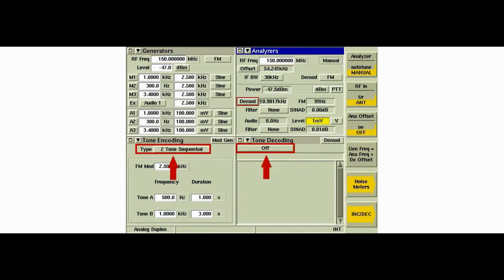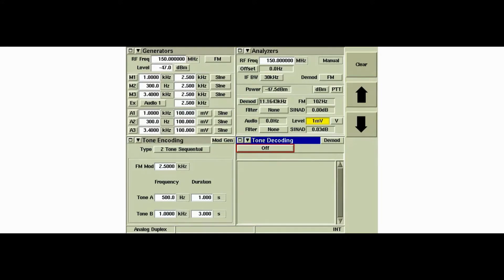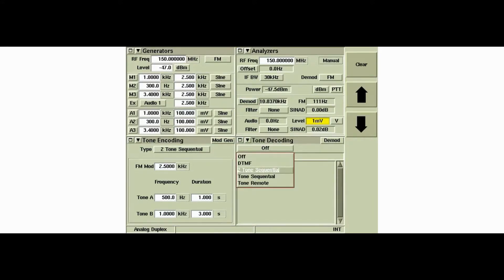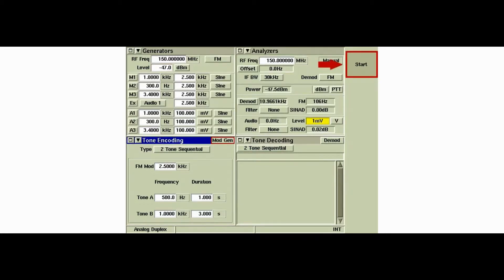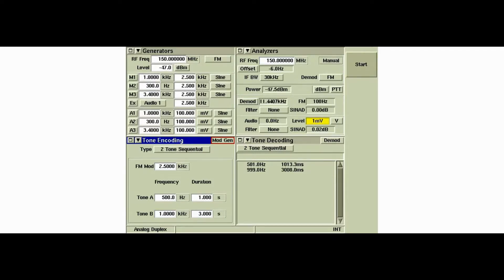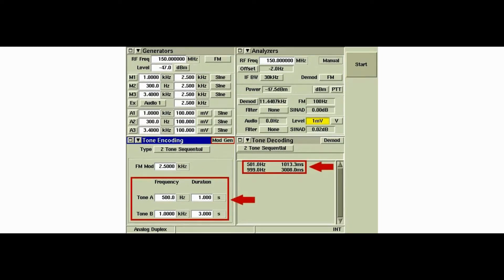The receiver is also set to the same frequency as the generator so it can decode the signal coming from the generator. The tone encoding is set to two-tone sequential, so we need to set the tone decoding to decode two-tone sequential. We'll select the tone encoding tile to access the start softkey to generate the program sequence. The instrument has successfully encoded and decoded a two-tone sequential burst.